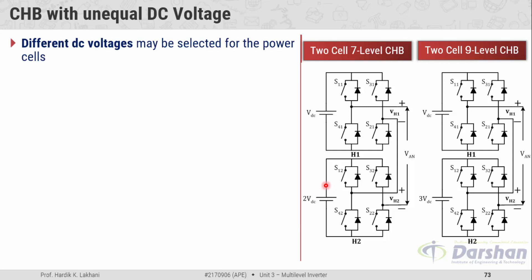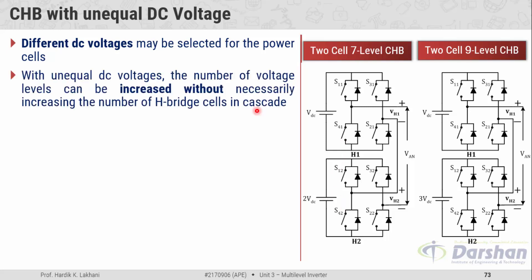By following the same principle, we can produce nine levels across a nine-level CHB having unequal DC voltage sources. Different DC voltages may be selected for the power cells. In the CHB with unequal DC voltage, we can use different magnitudes of DC supply for H1 and H2. With unequal DC voltages, the number of voltage levels can be increased without increasing the number of H-bridge cells — that is the key benefit of this unequal DC voltage concept.